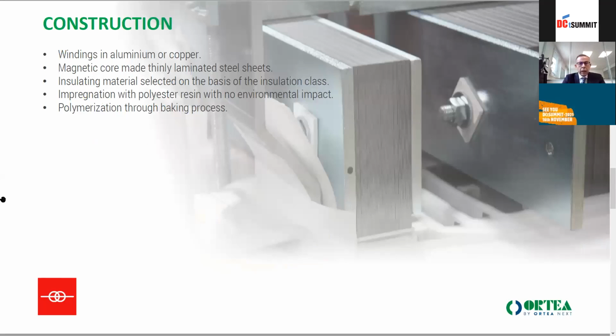The construction is very easy. As you can see, we do have winding in aluminum or in copper. We do use magnetic core in grain-oriented or standard laminated sheets, insulation material according to the project. In impregnation, we do use polyester resin, which is polymerized in oven later on. We do use a special polyester resin, but it is made under pressure, so it is under vacuum or under pressure and then polymerized in oven.